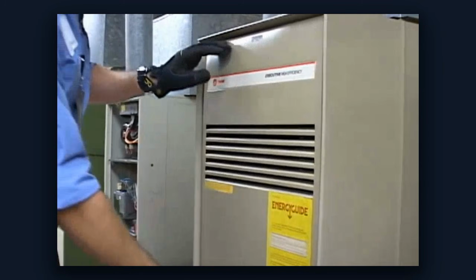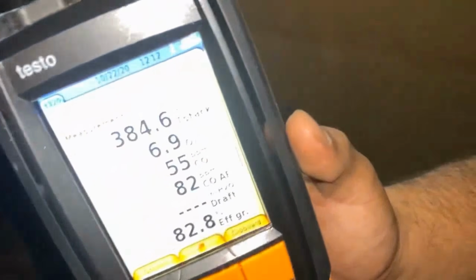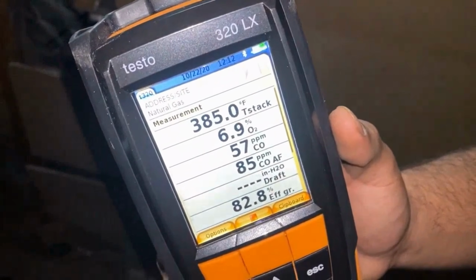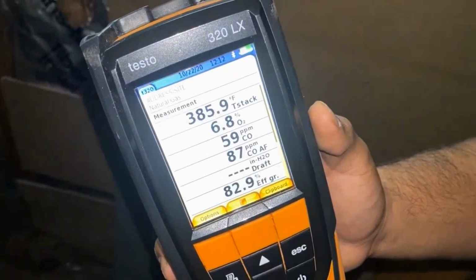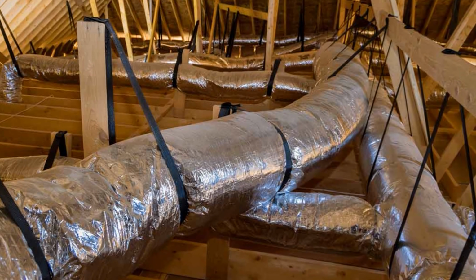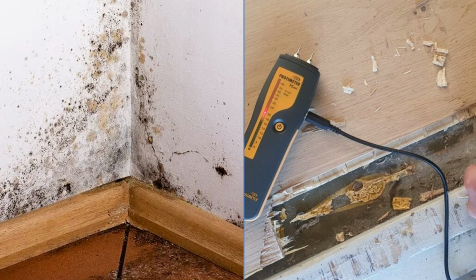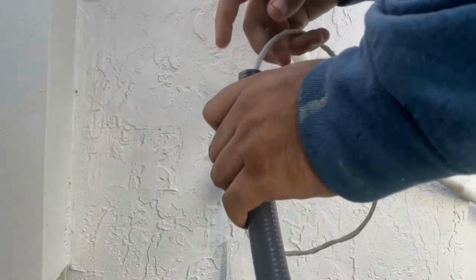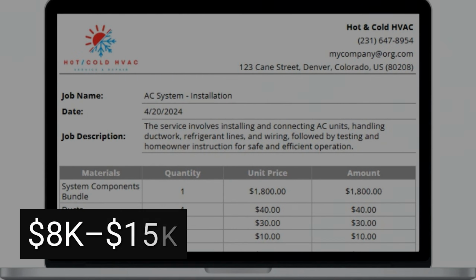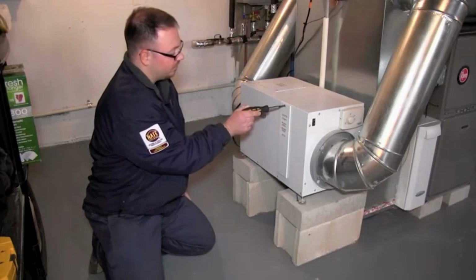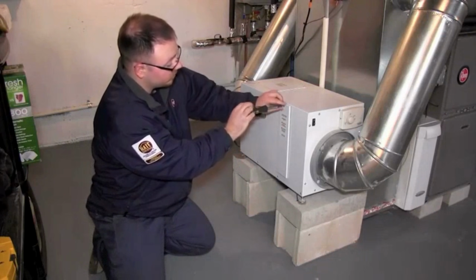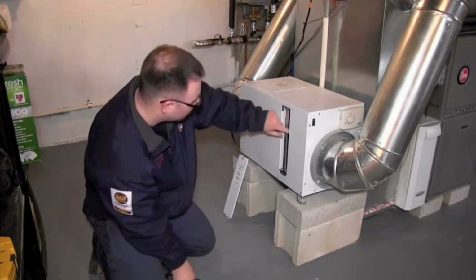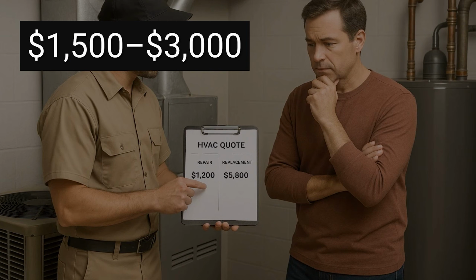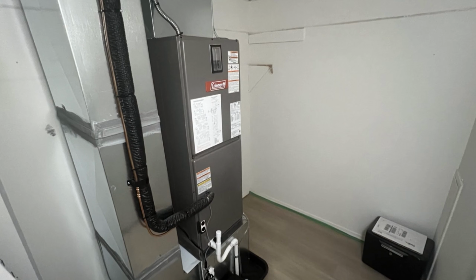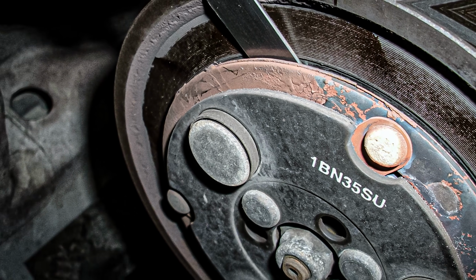After you move in, get your system tested. A qualified technician with a combustion analyzer and airflow hood can verify whether your equipment is delivering its rated tonnage and whether your ductwork is sized to move the right volume of air. Undersized ducts compound an undersized unit. Many production homes have both problems simultaneously. If your system is undersized, you have 2 options. You can upsize the equipment, a new condenser and evaporator coil, at a cost of $8,000 to $15,000 installed. Or you can add a whole home dehumidifier to the existing system, which costs $1,500 to $3,000 installed and will at minimum solve the humidity problem and reduce compressor runtime, extending the life of the undersized unit. Neither option should have been necessary. Both are cheaper than waiting for the compressor to fail.